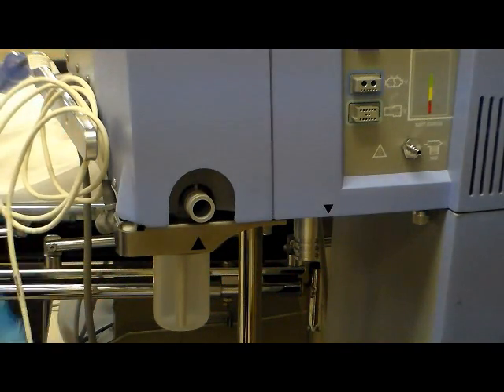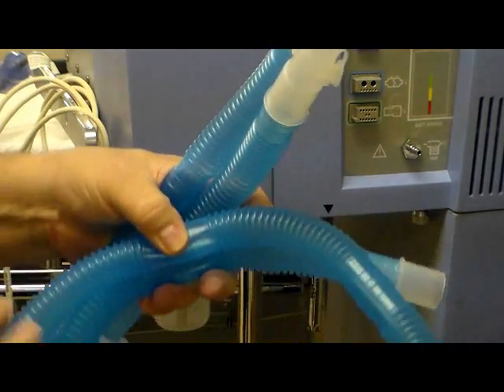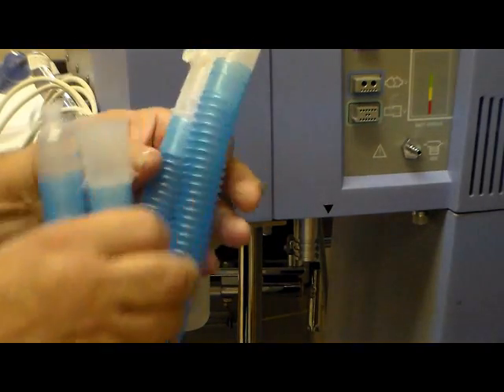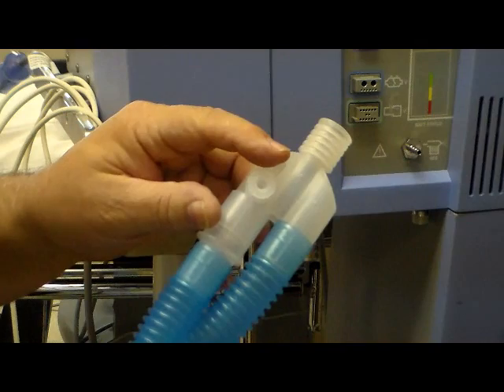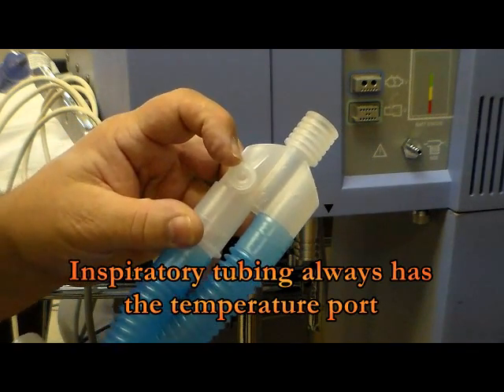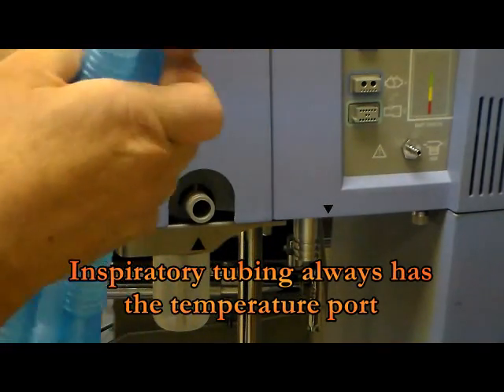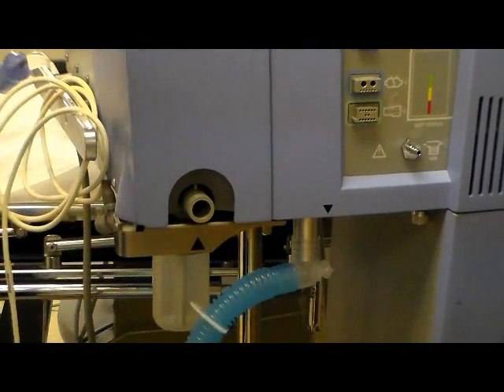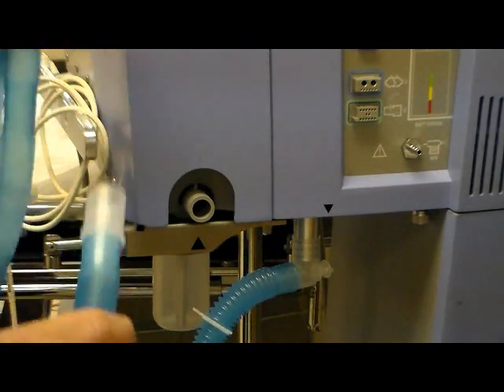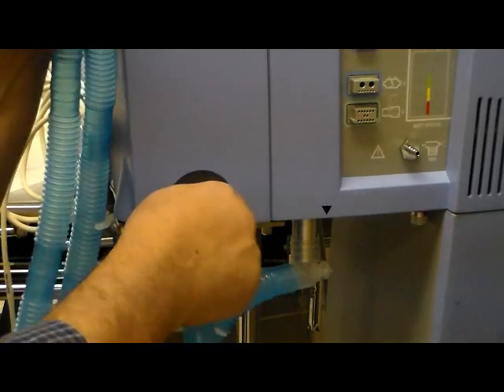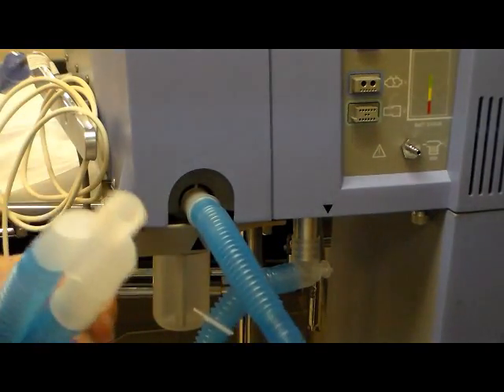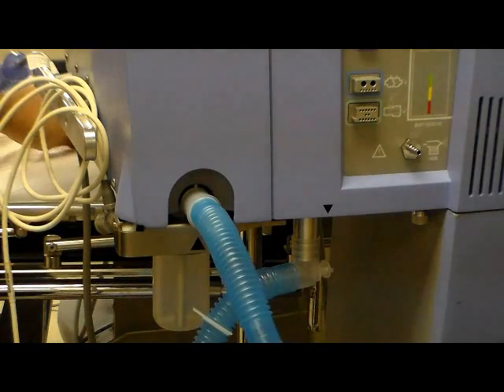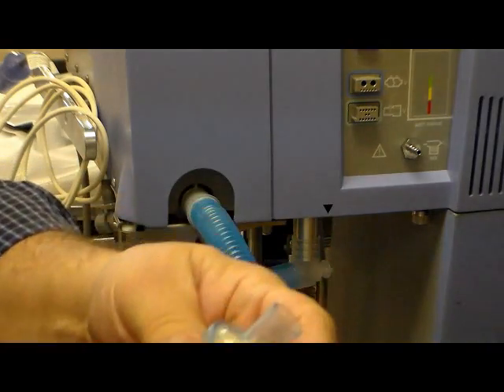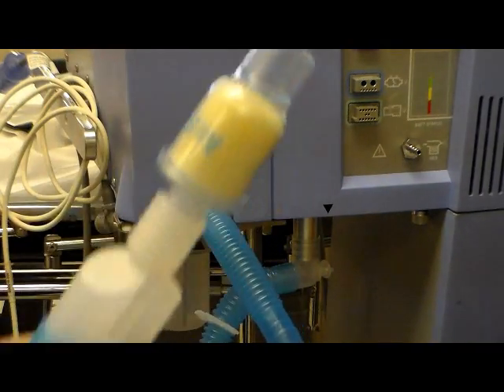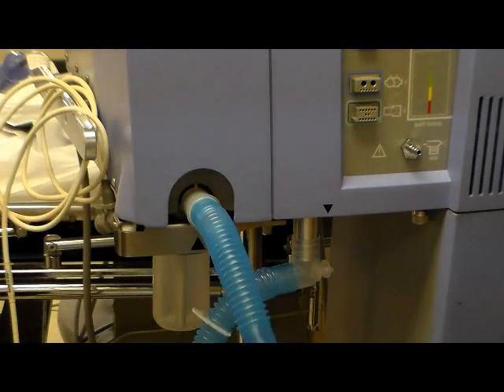Okay, so the next step is let's hook up our expiratory and inspiratory tubing. How do we know inspiratory from expiratory? Always, when you have this temperature probe port, always put that on the inspiratory side of the ventilator, so that if you do go to a heated humidifier, you do not accidentally have the temperature probe sensing the expiratory flow. Okay, so with this ventilator, we're just going to use an HME, and we're going to place that right there, and that'll be our humidity for this ventilator.